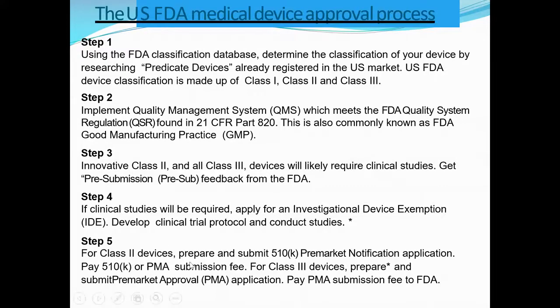Then for a class 2 device, prepare and submit the 510K pre-market notification application, that is pay the 510K fees, or the PMA submission fees. And for a class 3 device, prepare and submit the pre-market approval application and pay the PMA submission fee to FDA. So for class 2, prepare and submit 510K. 510K is like what we call IND, NDA, ANDA. For category 2 medical devices in US FDA, we call it the 510K pre-market notification application. This number is very important because it starts with K, like K0001. Like in ANDA, how we get a number from US FDA, when we submit a 510K application, we get a 6-digit number from US FDA starting with K, and that is why it is called a 510K application.